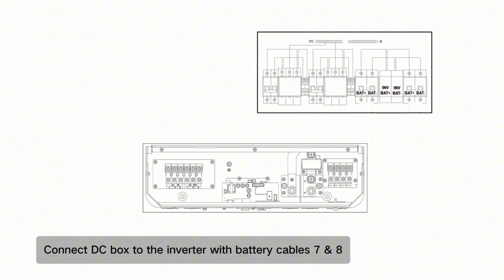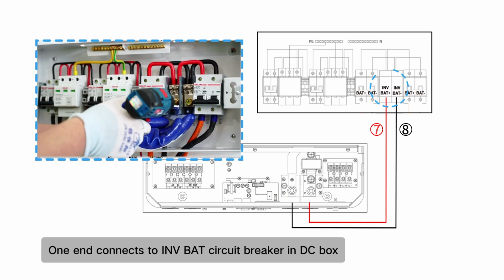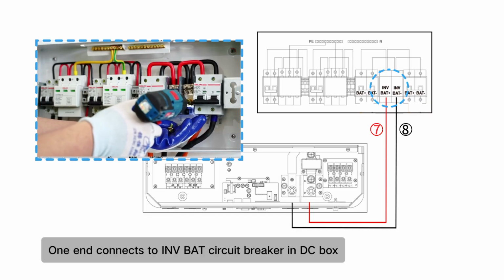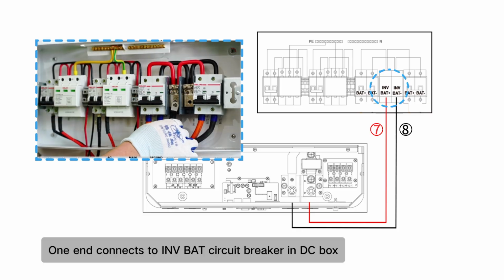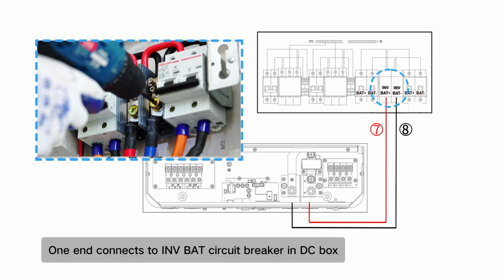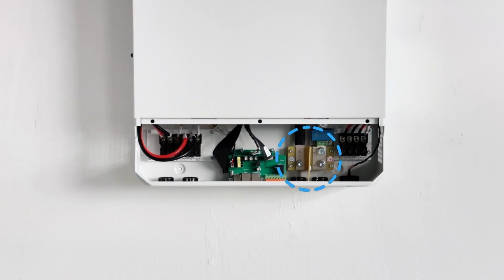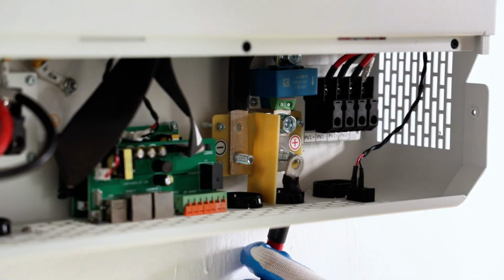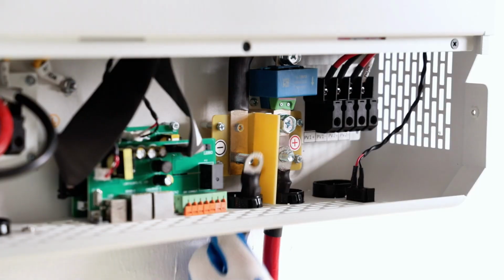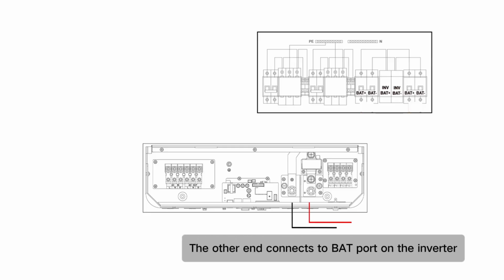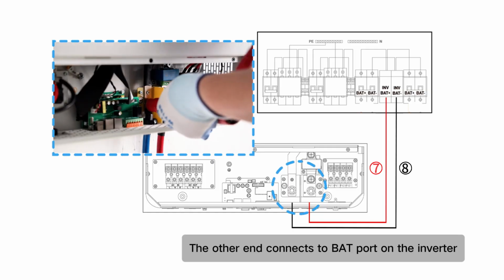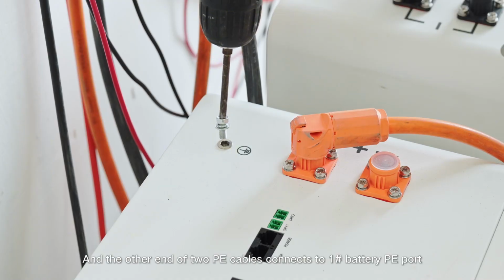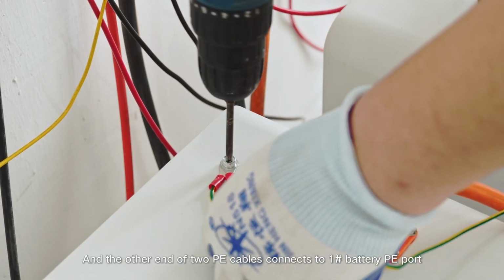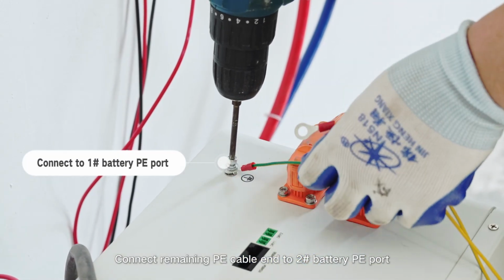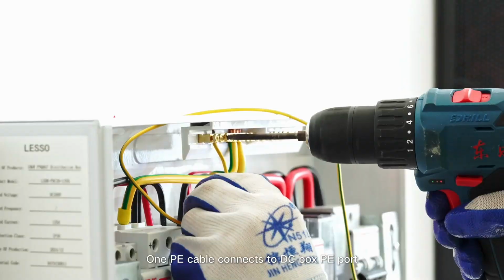Connect the DC box to the inverter with battery cables 7 and 8. One end connects to the INVBAT circuit breaker in the DC box. The other end connects to the BAT port on the inverter. And the other end of 2 PE cables connects to the 1-number battery PE port. Connect the remaining PE cable end to the 2-number battery PE port. 1 PE cable connects to the DC box PE port.